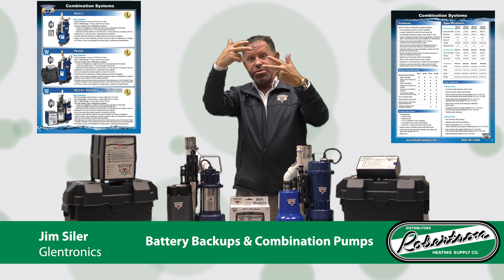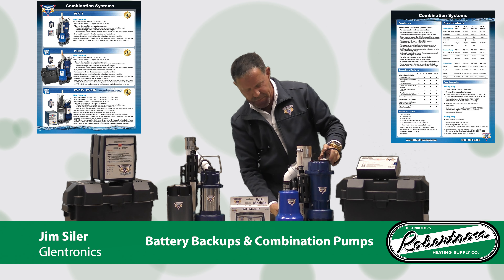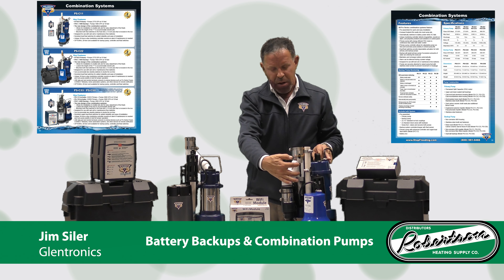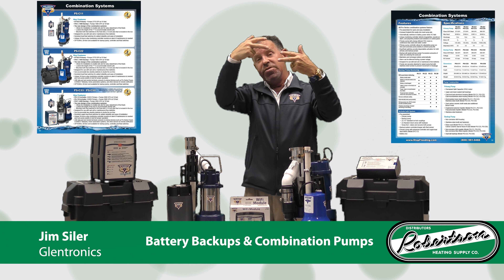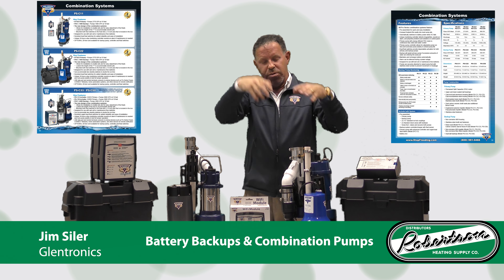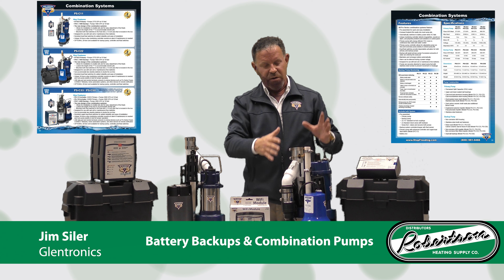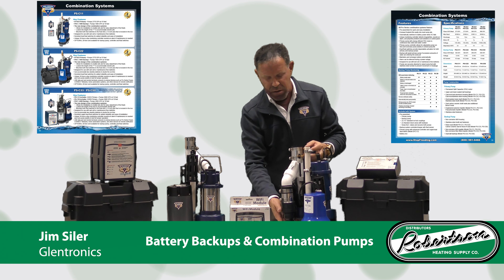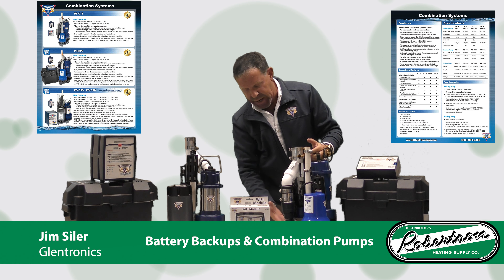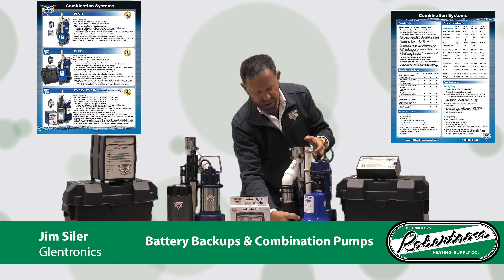Four floats instead of two — a cage float system for your primary pump with a bottom float that activates when water hits it and a top float, plus a dual float system for the backup pump too. If the primary floats don't activate the pump, these two will turn it on, and the pumps will also work in conjunction, giving you a total pumping power of 2,770 and 1,850 GPH in the event of a lot of water. Everything is packaged on the stand with check valves and wet poles pre-installed.